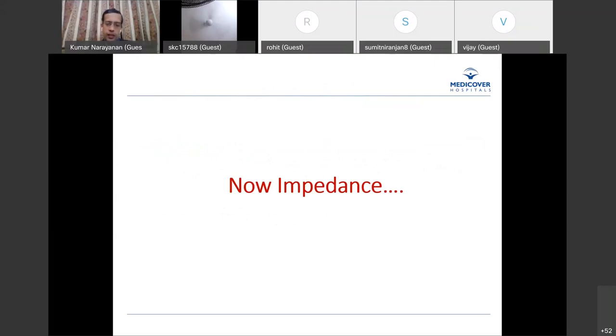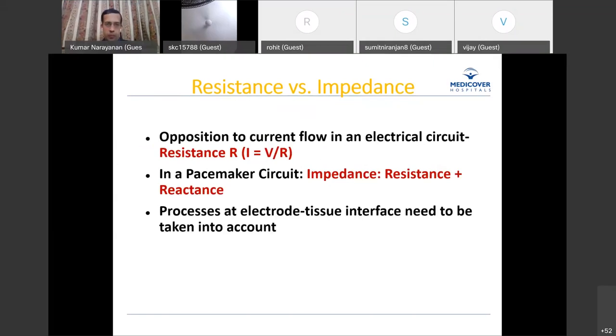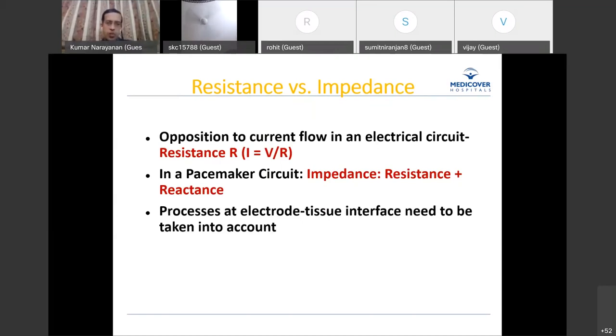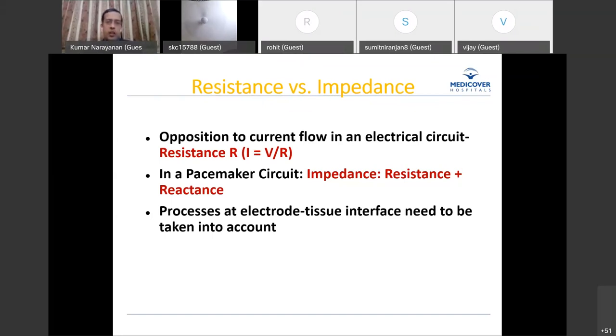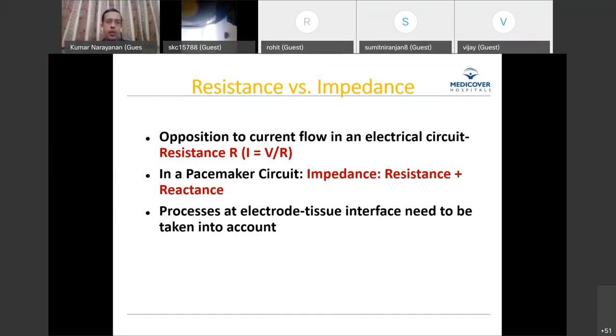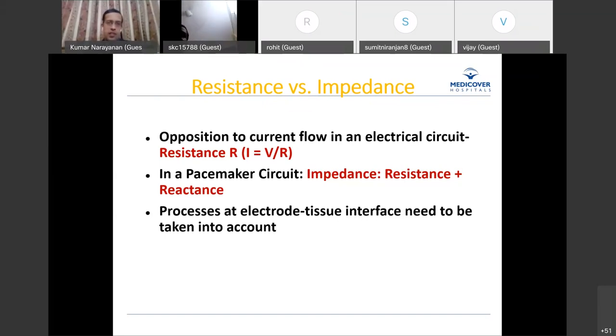Now let's look at impedance. Every electrical circuit has resistance, but in a pacemaker circuit the impedance has two components: the electrical circuit resistance plus reactance — the processes at the electrode-tissue interface which must be taken into account. Unlike a simple home electrical circuit, here we have an electrically active living tissue interacting with the circuit, adding its own dynamics. That is why we use the term impedance rather than just resistance.